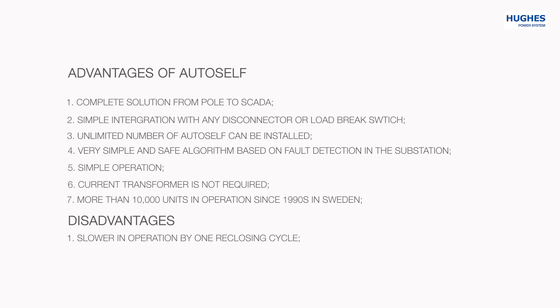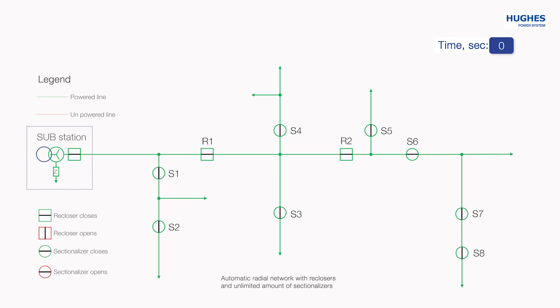AutoSelf opens the disconnector or load break switch when there is no power in the line, but in reality customers are out of power for a very short time. Operation Principle of the AutoSelf: let's take as an example a typical radial network scheme. It contains a substation on the left side, two reclosers marked R1 and R2 in the trunk line, and eight sectionalizers marked S spread in both trunk and spur lines. A fault occurs between sectionalizers S7 and S8.